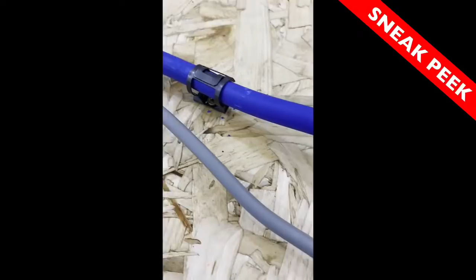The normal application for this is for overhead lines where you might have a bundled cable. A lot of the time where people get rid of the TT in rural properties and suddenly become TNCS or PME earthed, you'll find these bundled cables, which are 4 conductors wrapped around, and they put these on, and that's how they tap off to the properties.